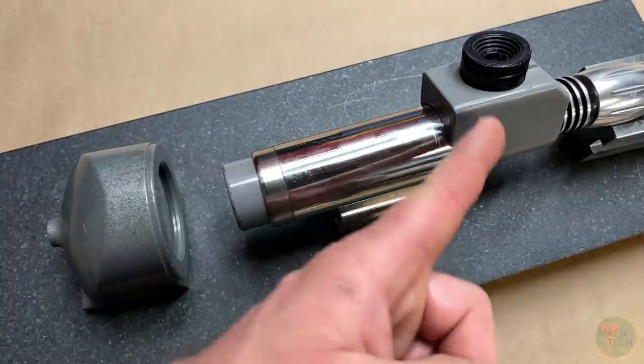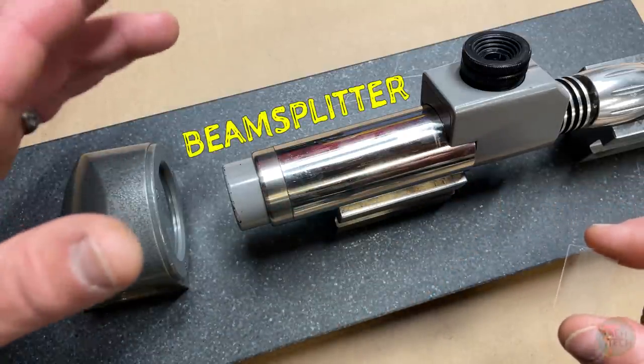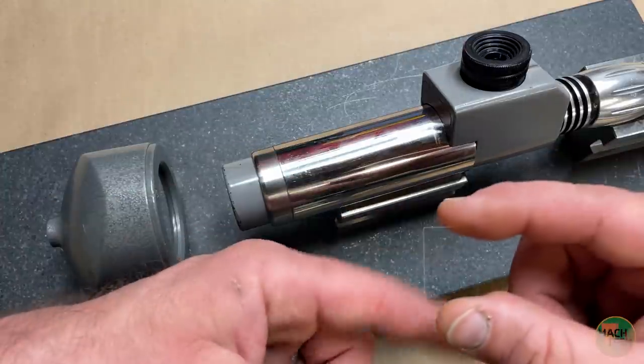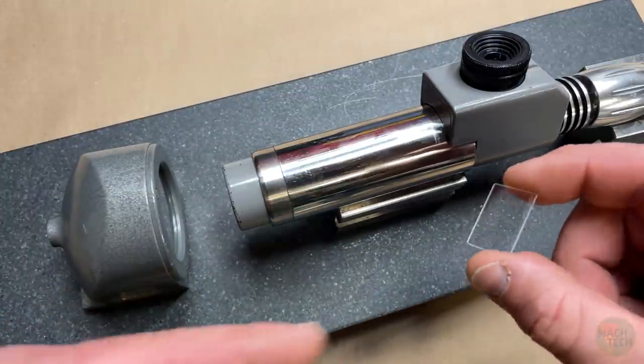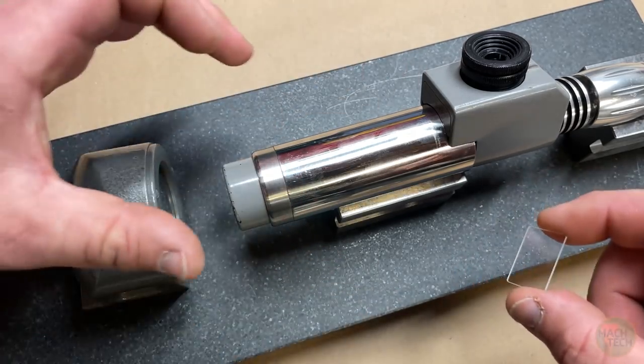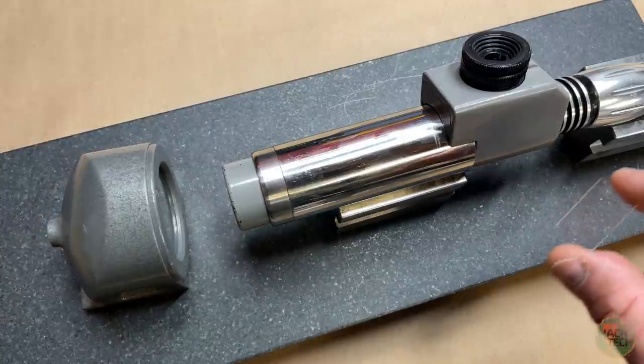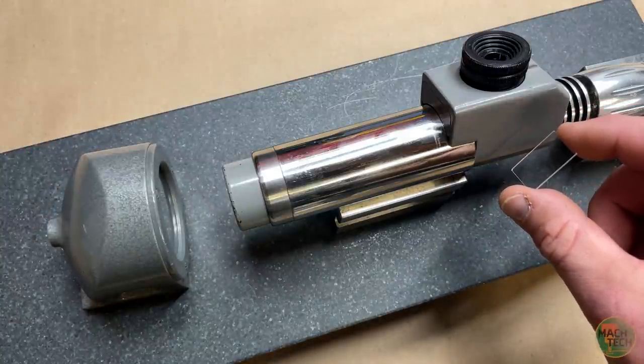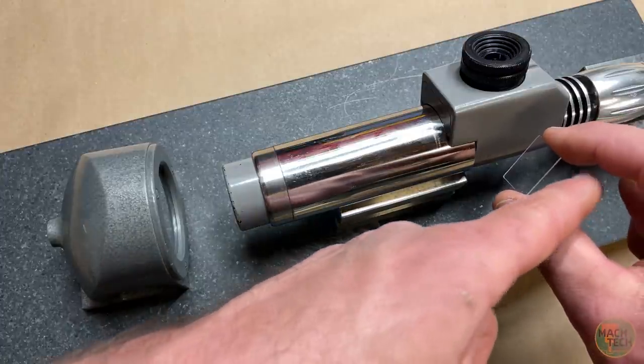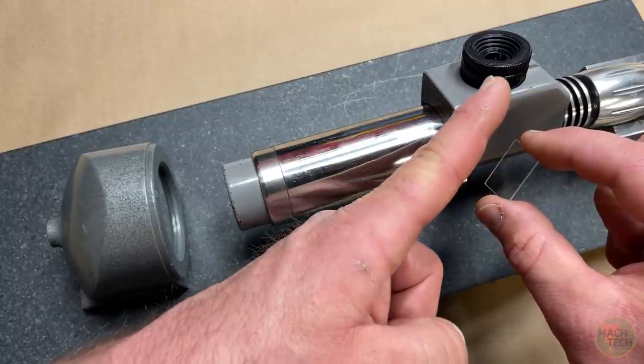But, and here's the big trick right here. In this housing, there is an optical component called a beam splitter. Sometimes people call them two-way mirrors, although that's kind of confusing because people also call them one-way mirrors. In any case, it's an optical device which is partially transparent and partially reflective. Sometimes they're plates like this one, but in precision applications, they're usually made out of two triangular prisms that are glued together on their hypotenuses to make a cube. But let's not go into that quite yet. The point is that the beam splitter is oriented so that the partially transparent, partially reflective surface is at 45 degrees to the optical path. So it allows light to travel in this direction from the light source, but the return light from the mirror is redirected at 90 degrees and it comes to a focus right about here.